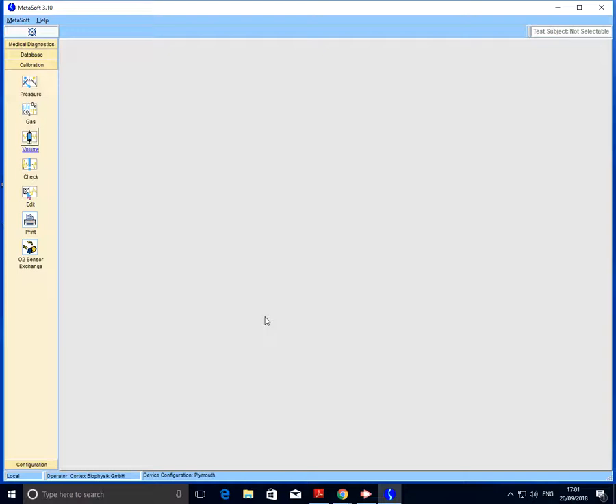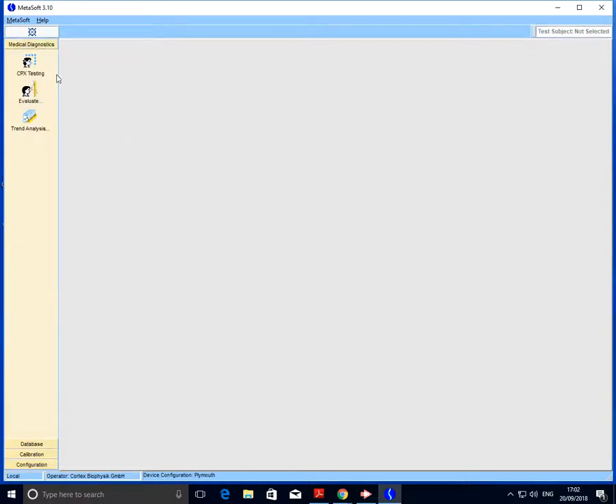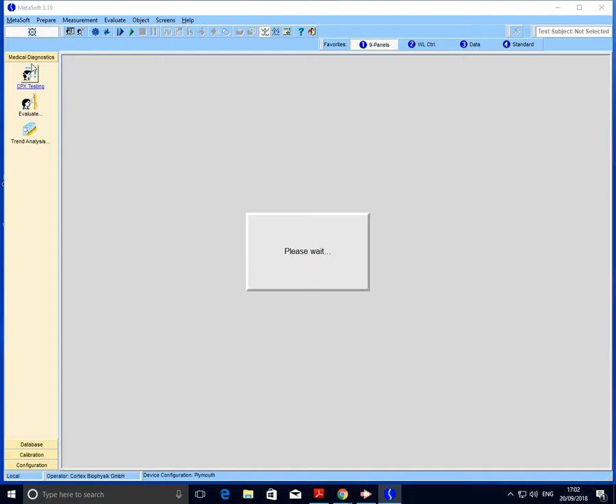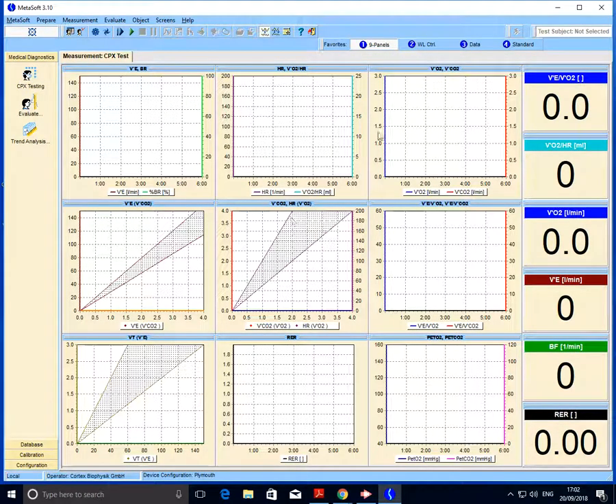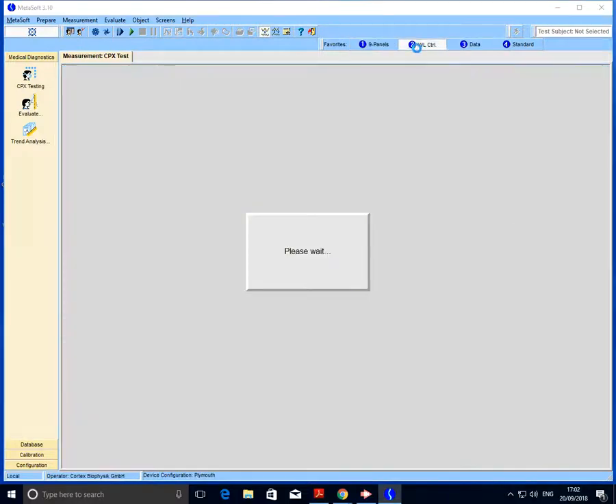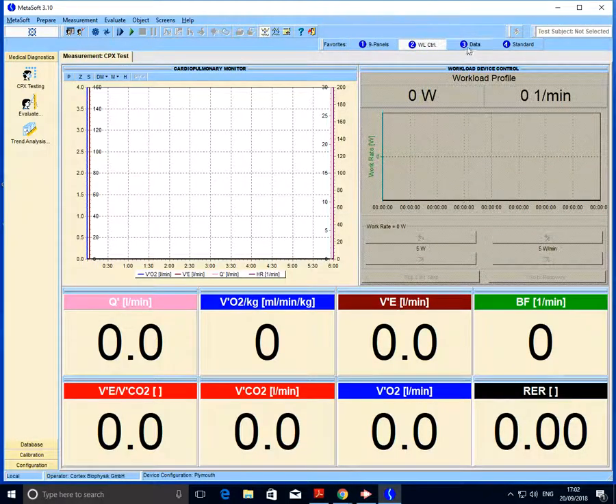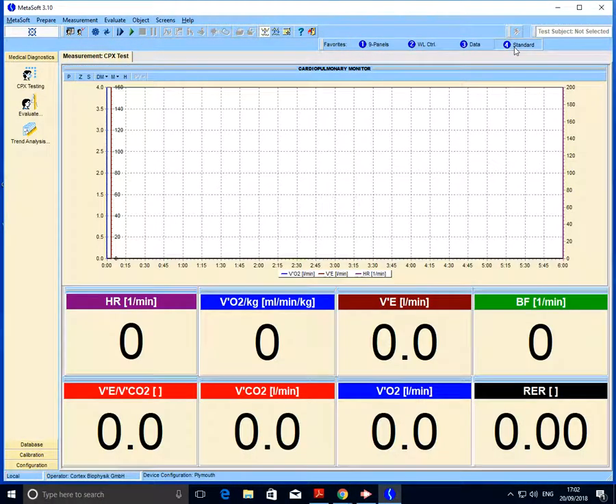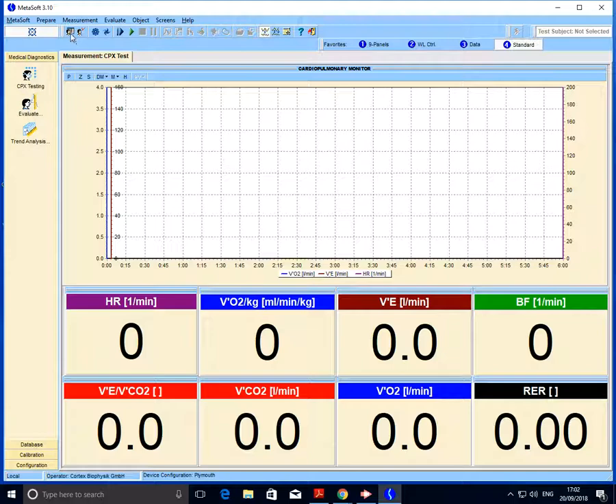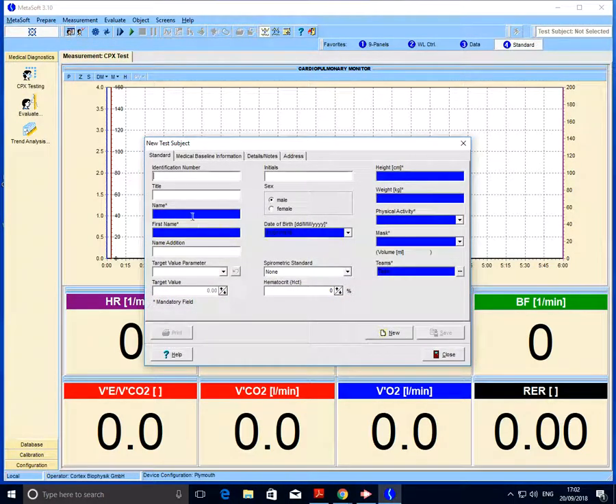So that's the three-stage calibration complete. In order to then quickly set up for a test, if we head to medical diagnostics and select CPX testing, we're initially displayed this nine-panel screen, but we can also toggle that display with the most common being the standard screen. Then enter our subject details. If we head to this icon, the idea now is that we enter the data into the blue required cells. Hope this has been useful. Thanks for watching.